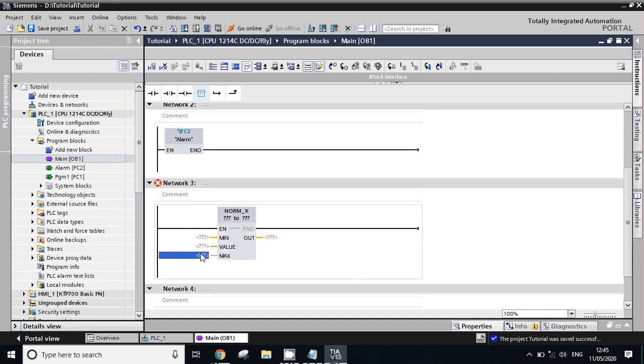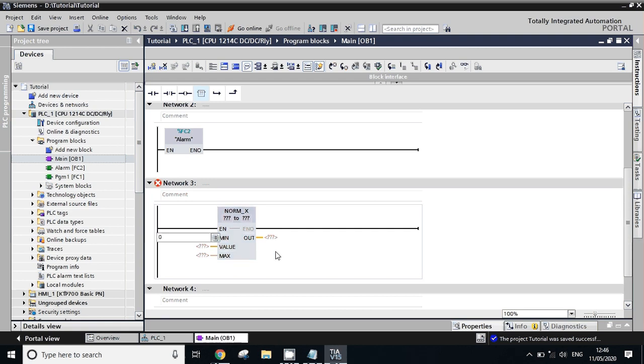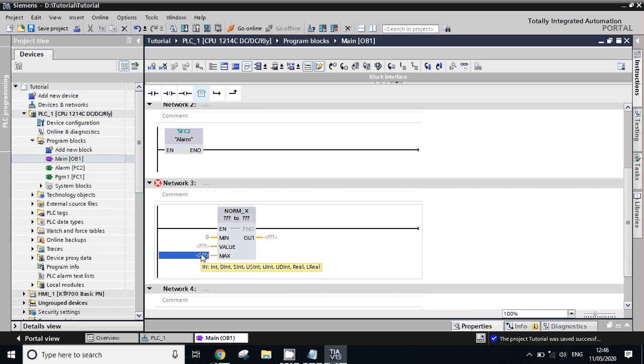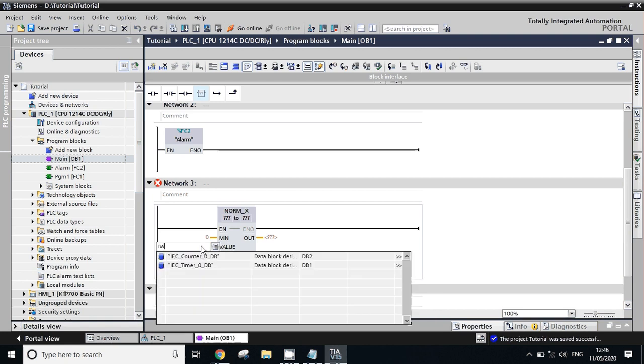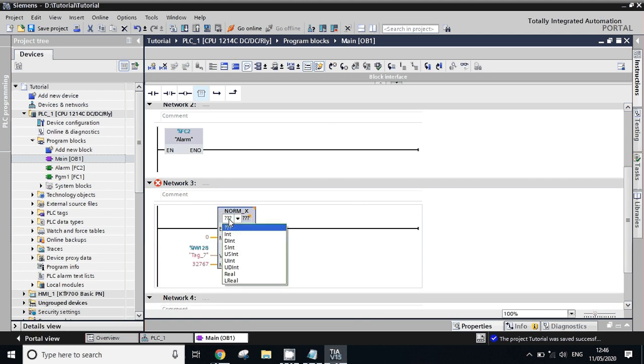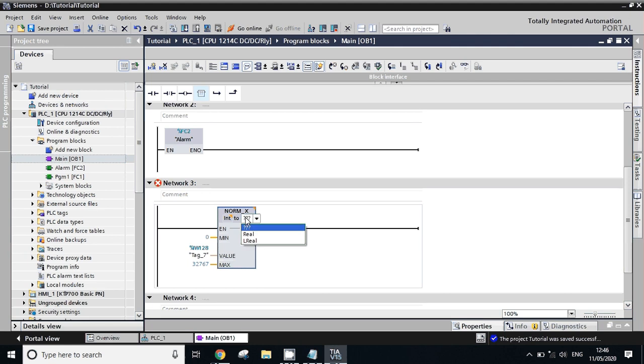What happens in any analog device? It gives us a value in pulses. It gives the value in 0 to 32,767. So we have to take minimum 0, maximum 32,767. And what's our input address? IW 128. Here we need to select data type: Integer to Real.